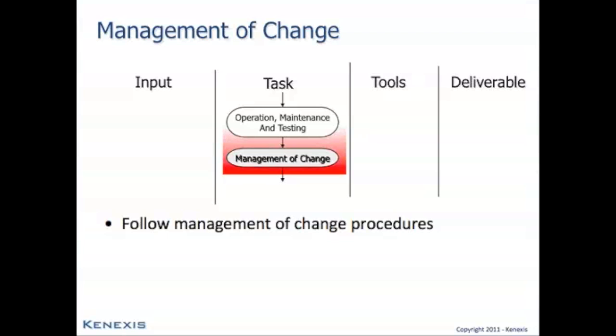So the scope of changes that will affect the fire and gas detection system's ability to achieve the tolerability of risk targets of an organization is wide. As a result, you're going to want to make sure that your existing management of change procedures for the facility include steps for review of all changes to determine if the fire and gas system is impacted by those changes. And if it is, the appropriate level of redesign and return to the appropriate steps in the safety life cycle of the fire and gas detection and suppression system are initiated by those changes.